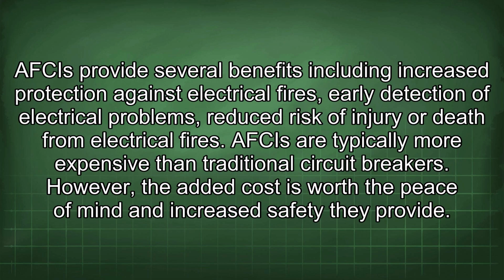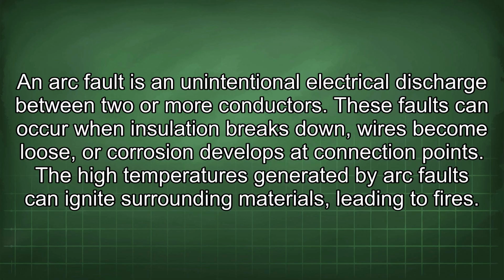AFCIs provide several benefits, including increased protection against electrical fires, early detection of electrical problems, and reduced risk of injury or death from electrical fires. AFCIs are typically more expensive than traditional circuit breakers. However, the added cost is worth the peace of mind and increased safety they provide. An arc fault is an unintentional electrical discharge between two or more conductors. These faults can occur when insulation breaks down, wires become loose, or corrosion develops at connection points. The high temperatures generated by arc faults can ignite surrounding materials, leading to fires.